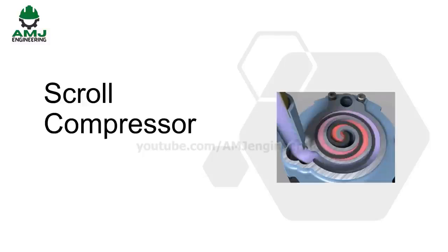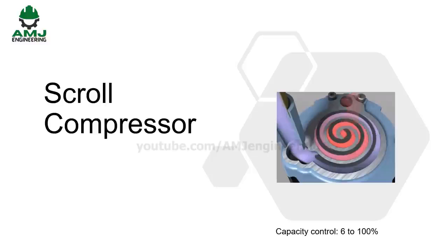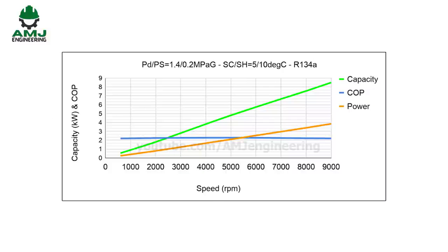The modern VRF technology uses an inverter-driven scroll compressor. Here is a short animation showing a cross-section of scroll compressors and their working principle. The inverter scroll compressor changes the speed to follow the variations in the total cooling and heating load. The capacity control range can be as low as 6% to 100%. Let's see how the inverter scroll compressor works. It is good to know that the relation between the speed and capacity is almost linear on scroll compressors. That is, double the speed and the capacity is almost doubled.